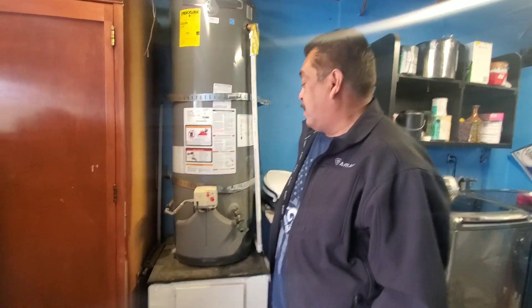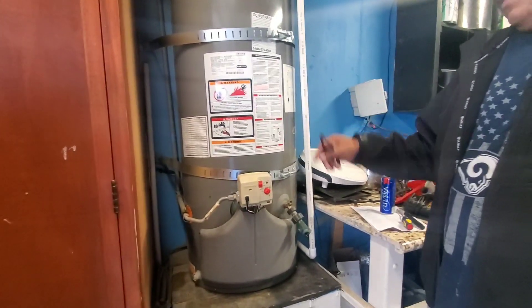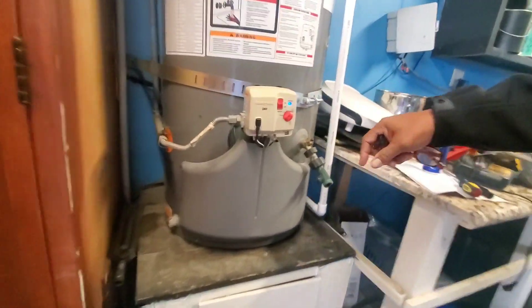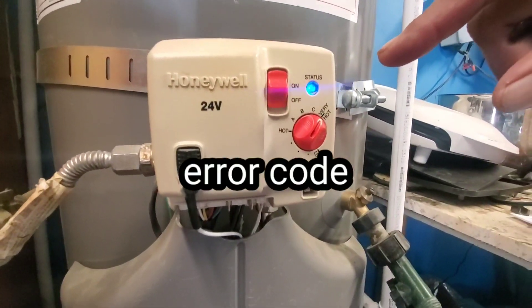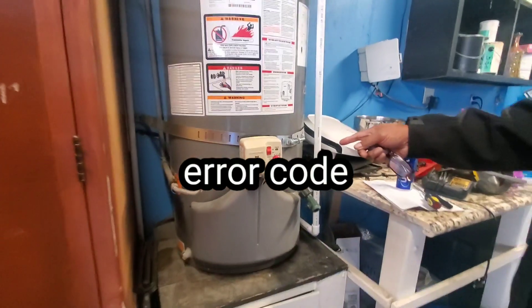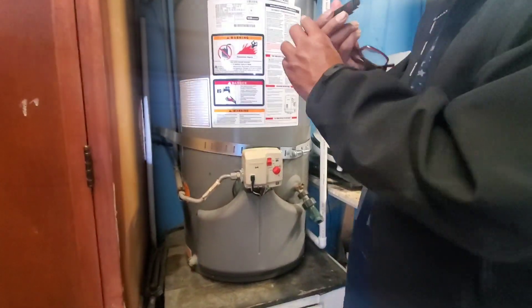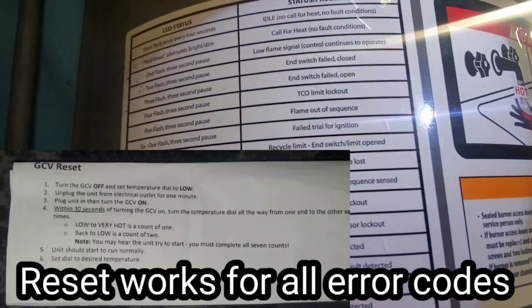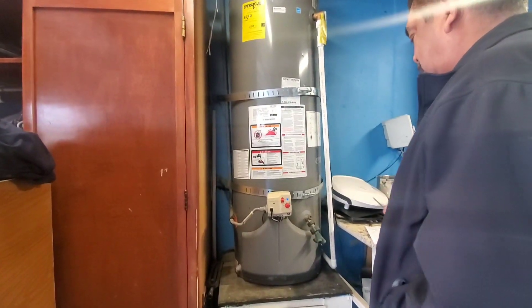I'm gonna do a quick tutorial on how to reset your Rheem water heater. It's not heating up, it's cold — you can't take showers. My valve is a Honeywell. You look at the flashes: you get seven flashes — one, two, three, four, five, six, seven — with a three-second pause, then another seven. I look at the board and it says seven flashes is your vapor sensor lockout. So I called tech support and they sent me instructions on how to reset it.